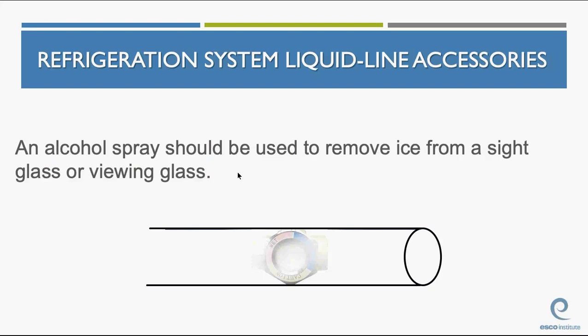Alcohol spray should be used to remove ice from a sight glass or a viewing glass. So if there's actual ice buildup on a sight glass, you can spray it with alcohol or dump rubbing alcohol on it. Don't use hot water. It has a chance of cracking that sight glass if it's too cold.